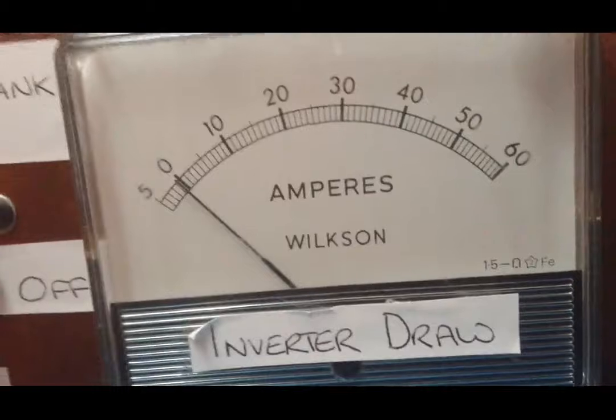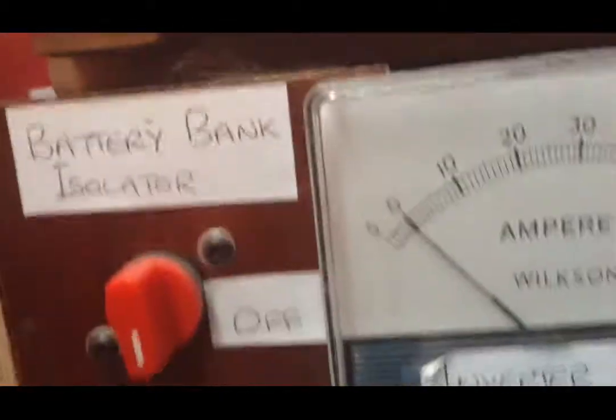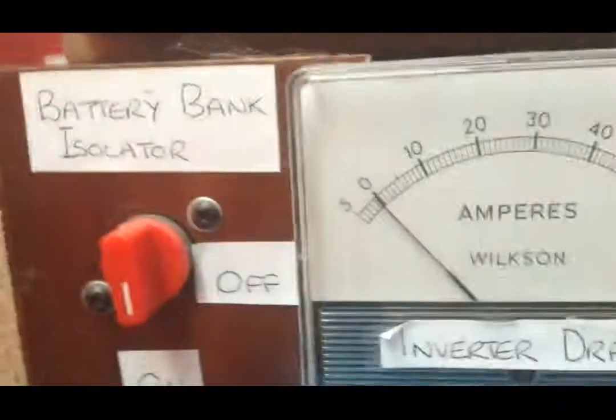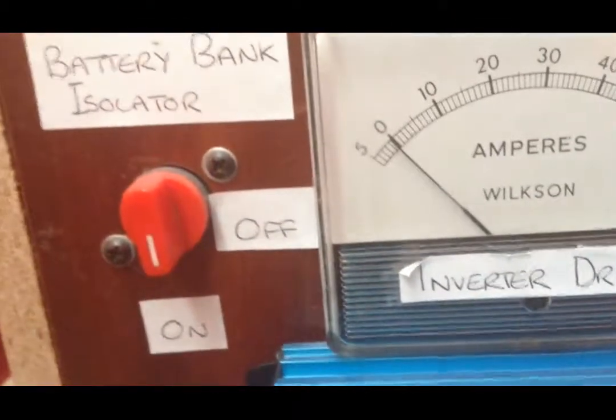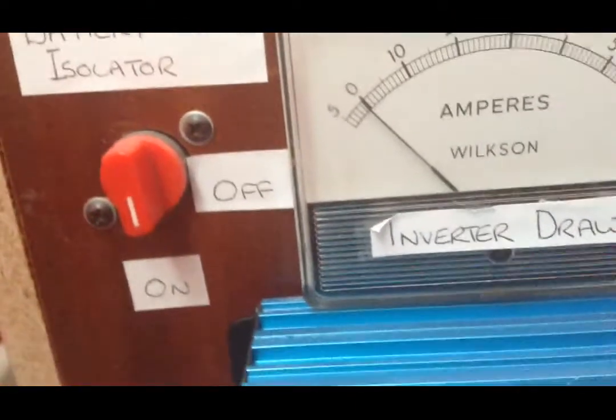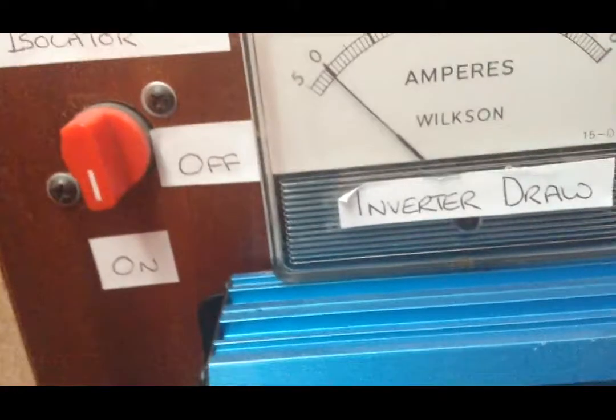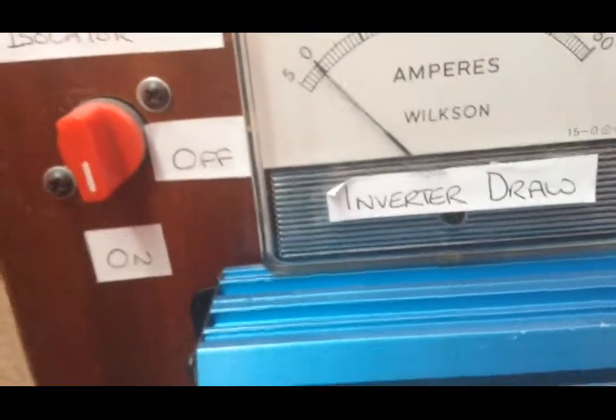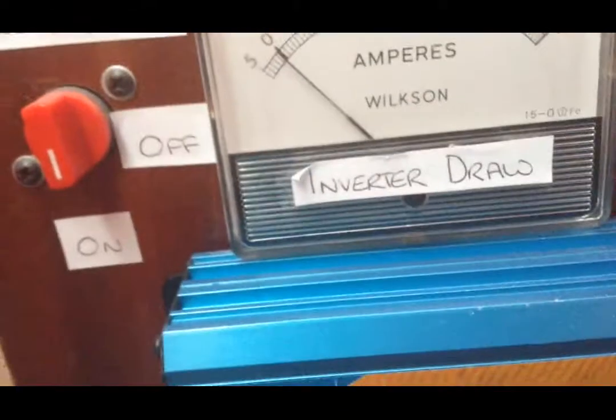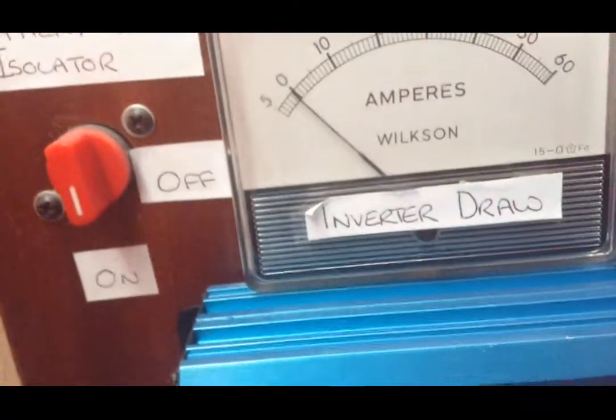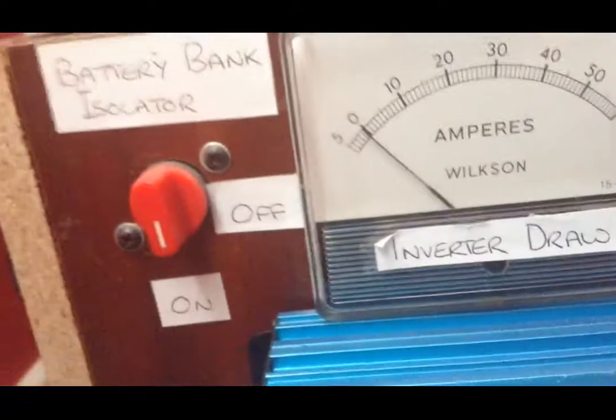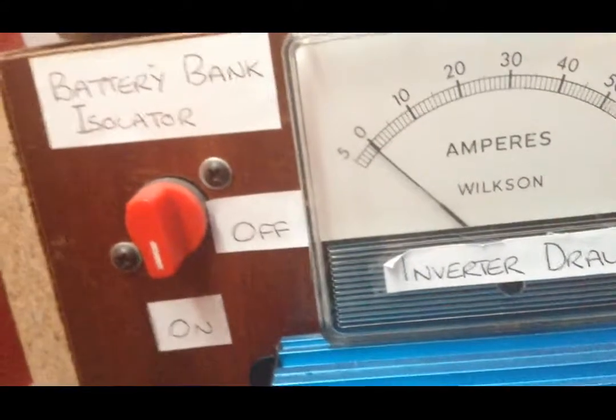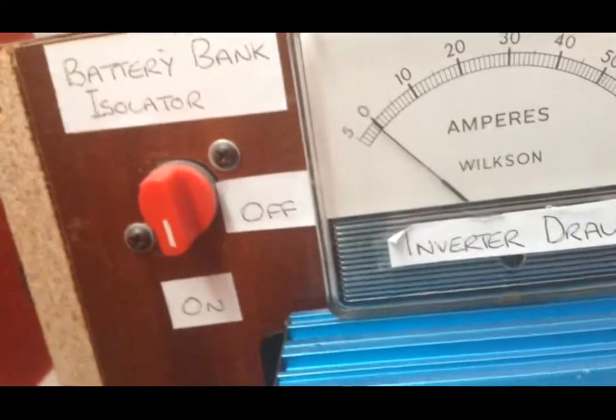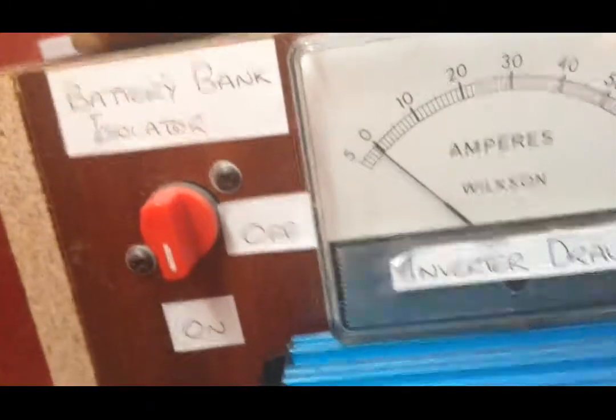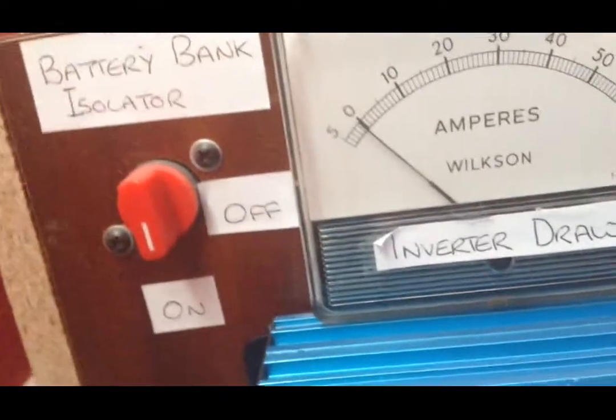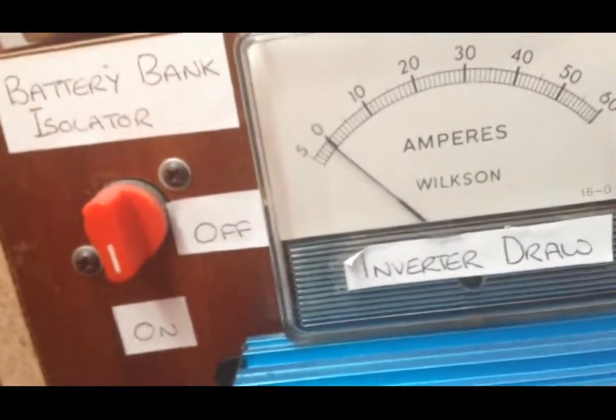Also, when you choose your battery main switch, it needs to be able to take the maximum current drawn by your inverter. In this case it's 30 amps, but if you have a bigger inverter, there will be something to consider. This switch here is actually out of a jump pack for starting a car, so that's a fairly chunky size switch.